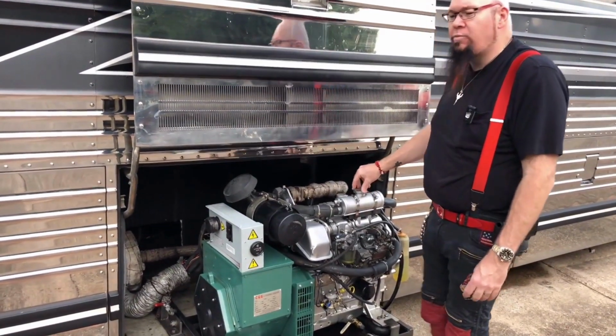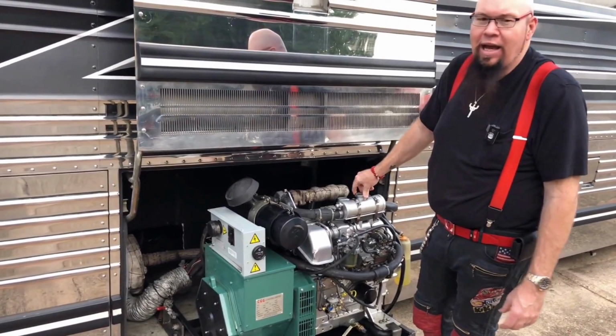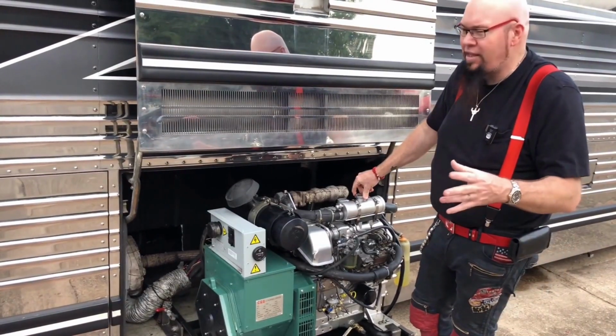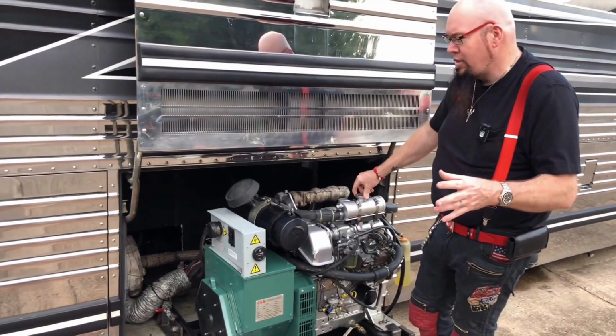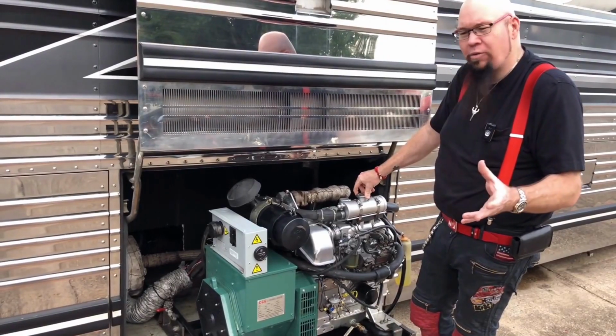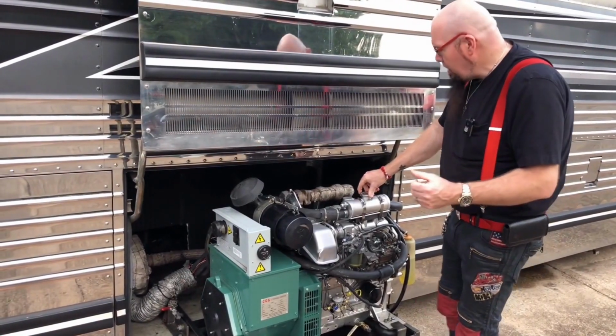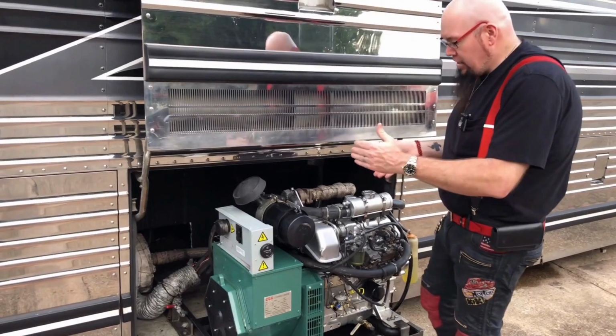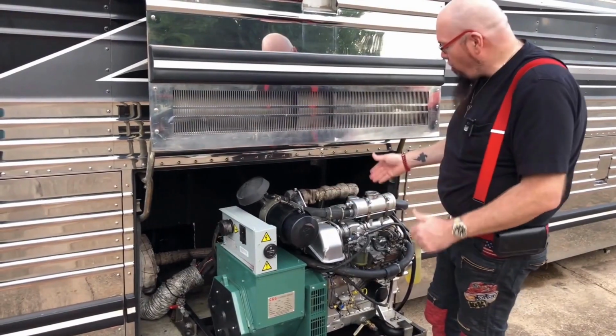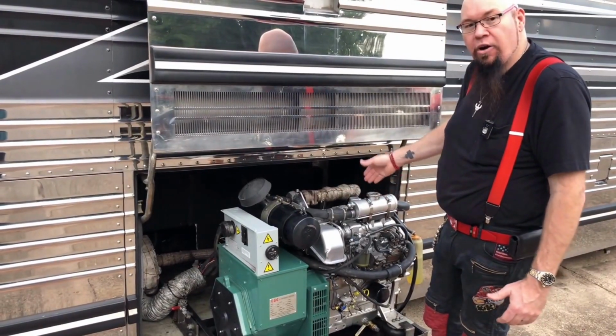These motors, a diesel motor, as you know, doesn't really run very high — they only run about 2,000 RPMs. I think the fastest a diesel motor can go is, I want to say 2250 or 2300 RPM, something like that. So the generator is asked to be set at an RPM of 1800 RPMs.